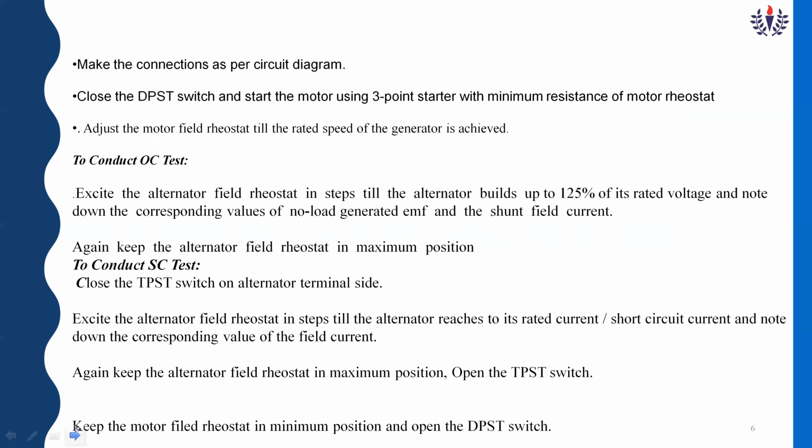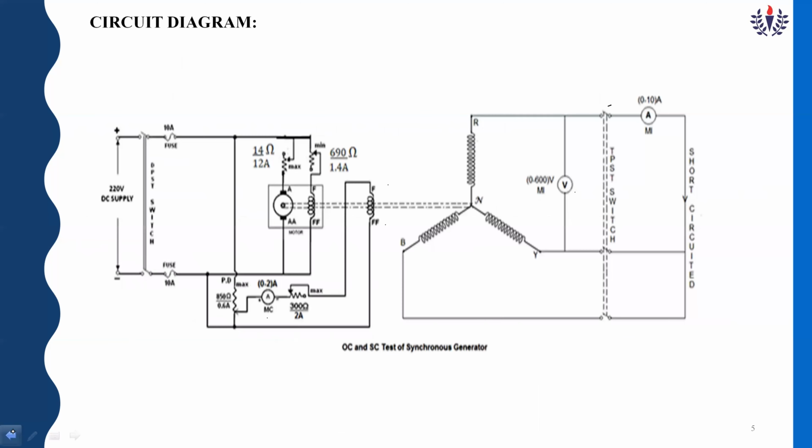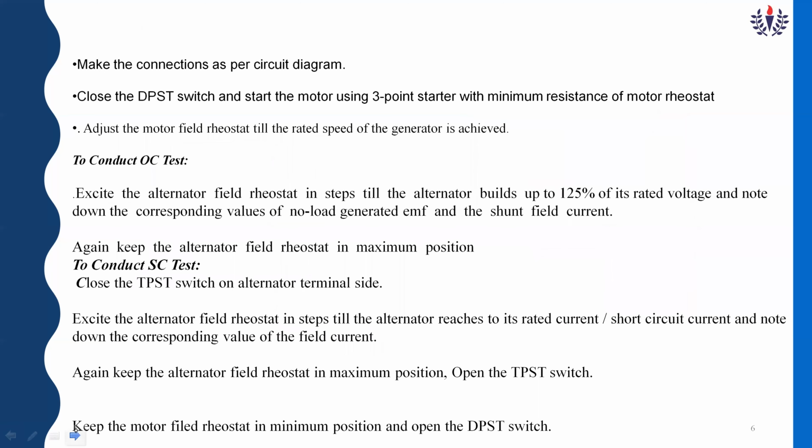So, what I have to do in the SC test is close my TPST switch. You can see the TPST switch here. I have to close this TPST switch, and then excite the alternator field rheostat in steps until the alternator reaches the rated current or short circuit current, and note down the corresponding value of field current.